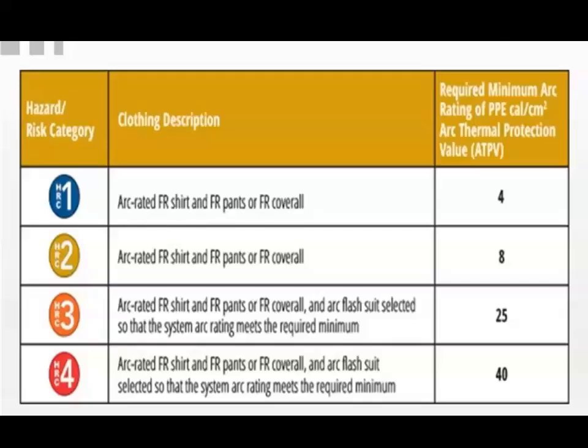Once you get into hazard risk category 3 and 4, the arc flash potential expands greatly. So more PPE is required, and more energy potential can be released. For hazard risk category 3, you have an arc flash FR shirt, FR pants, FR coverall, and an arc flash suit selected so the system arc rating meets the required minimum, and any additional PPE required for that piece of equipment. And for a hazard risk category of 4, an arc flash FR shirt, FR pants, FR coverall, and arc flash suit selected so the system arc rating meets the required minimum.